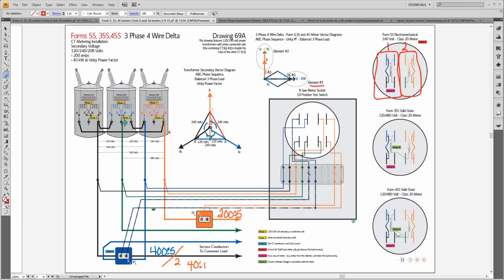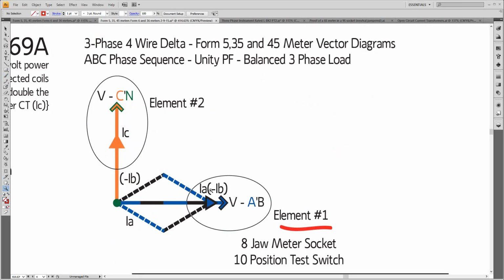So those two currents combine, again, as I see them, the direction and the magnitude will be exactly the same here. Direction is the opposite, but the magnitude will be exactly the same. So IB is here, minus IB there. And then these two currents are being added together. This is the addition of them through vector addition. If I take minus IB and shift it over here to IA, and put it there, I end up with a resultant current inside of that CT. That is the combination of those two, and I'll zoom in on that one so we can see a little better, as IA minus IB current is what that current is, and that's the summation of those two.